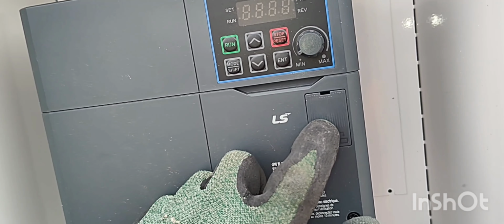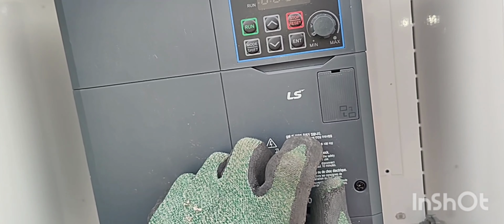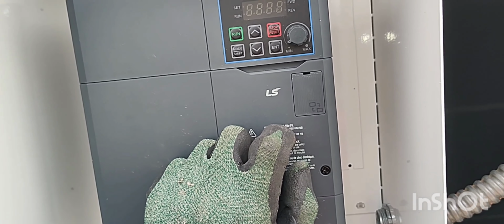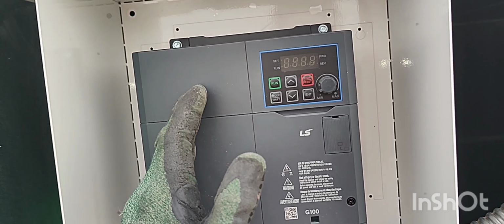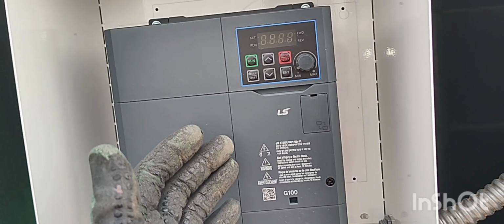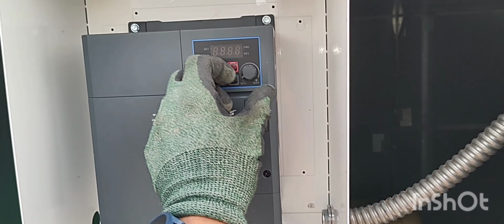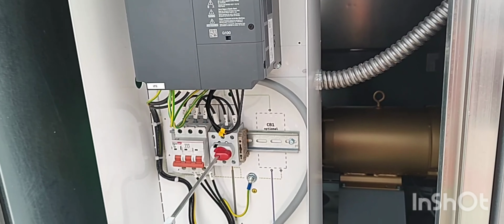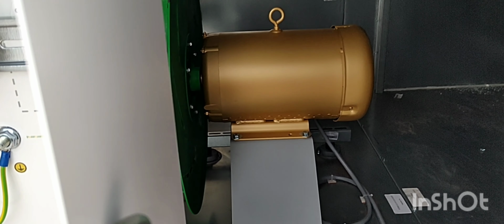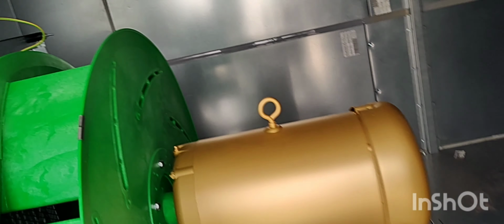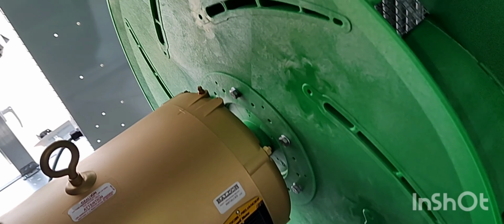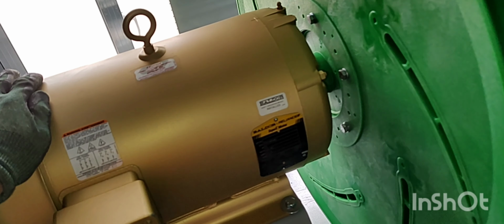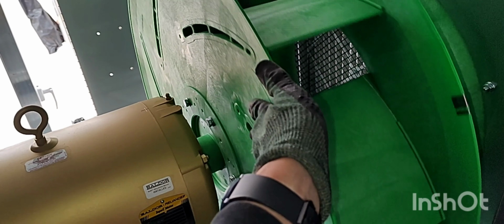This little plate right here, if you access that, you can run Cat 6 or Cat 5 to it. And you can remote control this VFD through a backbone with low voltage controllers. Or you can set it manually. And then we can size accordingly for this blower. So let's climb in here. Here is the fan motor. This spins this guy right here, which blows the air through the whole entire building.